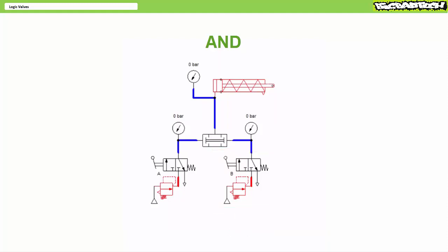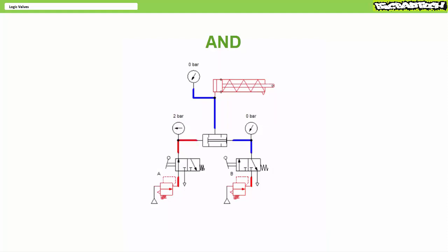Recall that an AND valve requires a pilot signal at both inputs A and B for there to be an output, and when both air pilots are present it selects the lowest of the two pressures. When neither A nor B receive an air pilot signal, the AND valve produces no output. When only A receives a signal, no output. When only B receives a signal, no output. Only when both A and B receive an air pilot signal does the AND valve produce output. You will note the AND valve selects the lowest of the two pressures, notably A at 2 bar.